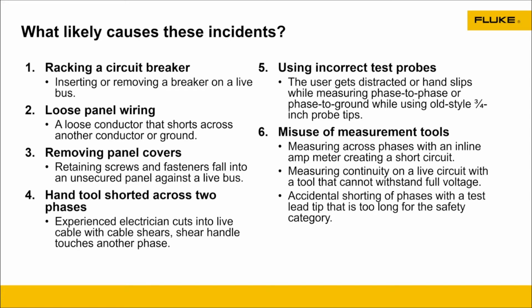But there could be loose paneling, even in a 240-volt split phase. If you had loose wiring, loose paneling, you would create an arc fault, an arc blast happening in that. Sometimes if you're removing a panel, maybe there was a loose wire, loose screws, and that would cause that. They short out on the line. Maybe you've already got that open and you're working, and a hand tool accidentally slips down across the two phases. And that's where we see another situation of that nature. That metal crosses the two and it happens.